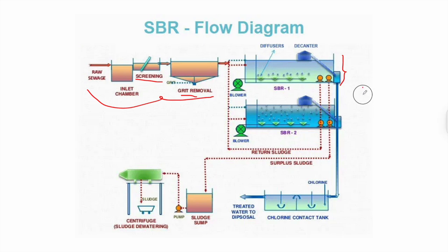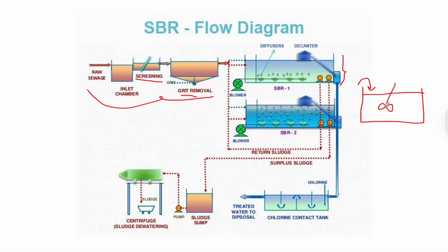Inside the SBR tank, the first step is the fill stage — filling the tank with wastewater. During this stage, a mixer can be used to create anoxic conditions, which are ideal for denitrification. Optionally, air diffusion can also be introduced during filling to promote early treatment activity.